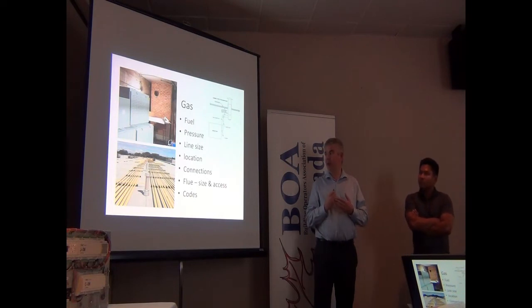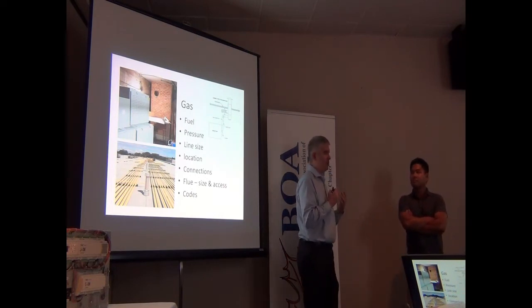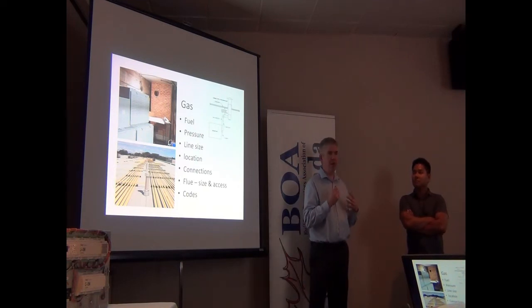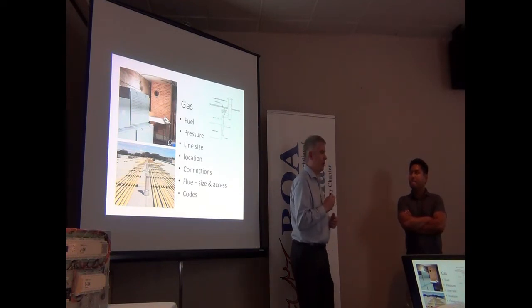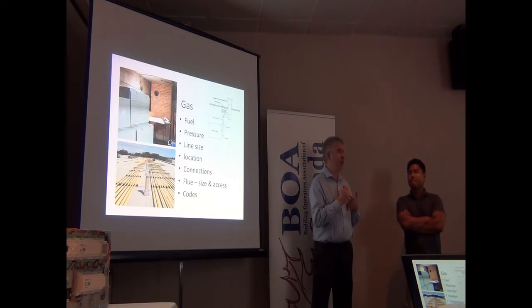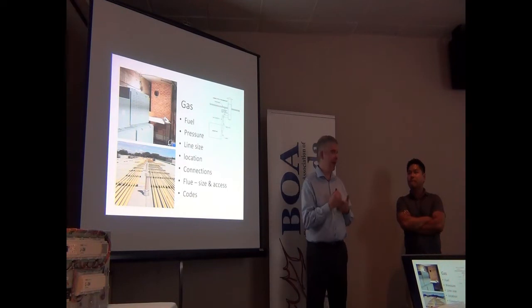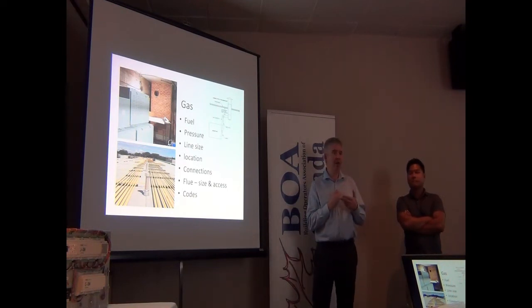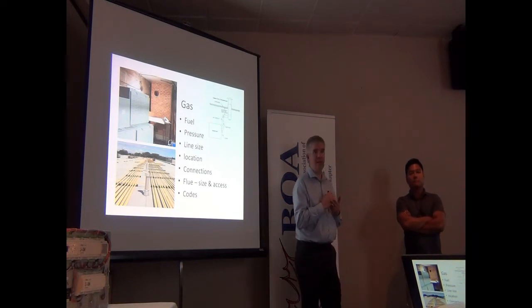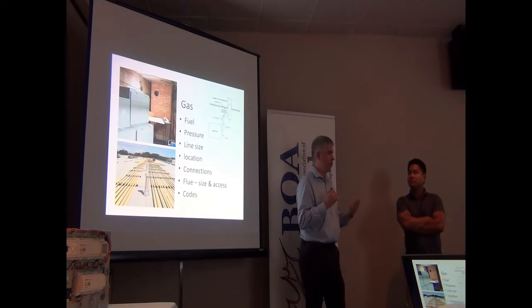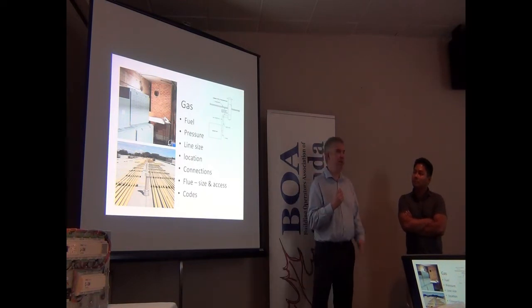And location is a big part of that too, because location of appliances can often move in retrofits, especially if they're smaller. Indoor mechanical rooms can get rearranged. Well, that can change your line sizing if you're suddenly 40 or 50 feet further from where the gas connection originally started at your one unit, and the heat exchangers are now in a different part of the building. And the other thing with venting, at least for appliances that are indoor, the material might have changed as well. You may have had something that was vented with a traditional A vent or B vent style, where now you have an appliance that has positive pressure and you need a stainless steel connection, stainless steel venting. So there's a whole bunch of considerations for what your gas and venting will look like that you have to look at ahead of time with your mechanical contractor.